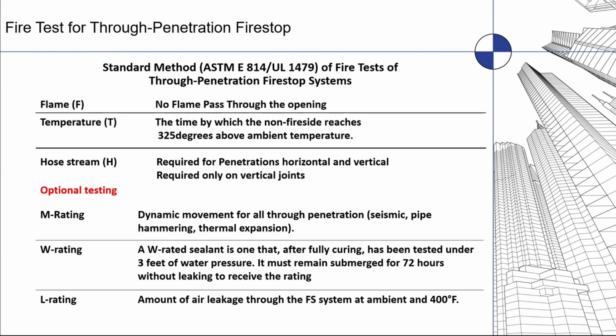And then there are some optional kinds of testing that are done. M rating, which is a movement rating, but it's really not like movement for expansion and contraction of an expansion joint. This is really something more like the movement of a pipe in a wall, or vibration or pipe hammering or something like that. And it could be related to seismic motion, but it's generally related to penetrations. W rating is for a water rating. So this has a particular standard to make sure that this product would hold up to a certain amount of water for 3 days. So 3 feet of water pressure attached to a floor assembly that would be in place for 3 days. And if it doesn't leak, then it has passed the W rating.